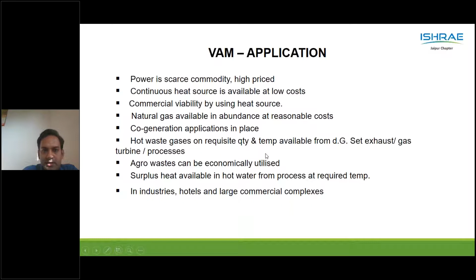An important criterion in deciding the application is that we also do an operational feasibility analysis. Suppose this is a steam driven VAM application. We have to note down what the steam cost is, what the power cost available is, and the number of hours it is operational. And in case there are savings with vapor absorption machines, we can go with the vapor absorption machine versus a compression system.